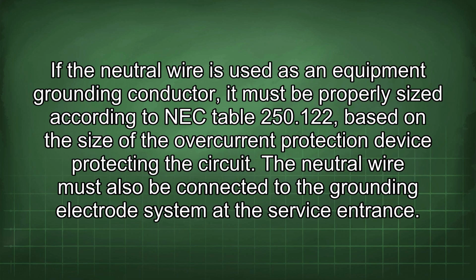If the neutral wire is used as an equipment grounding conductor, it must be properly sized according to NEC Table 250.122, based on the size of the overcurrent protection device protecting the circuit. The neutral wire must also be connected to the grounding electrode system at the service entrance.